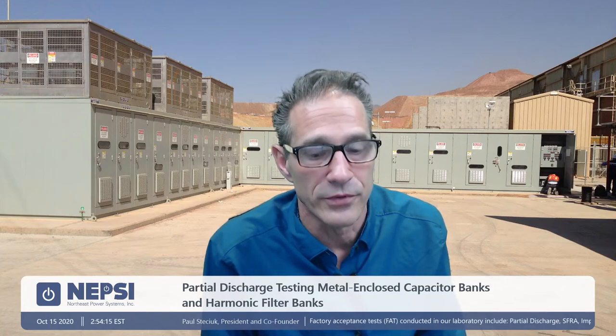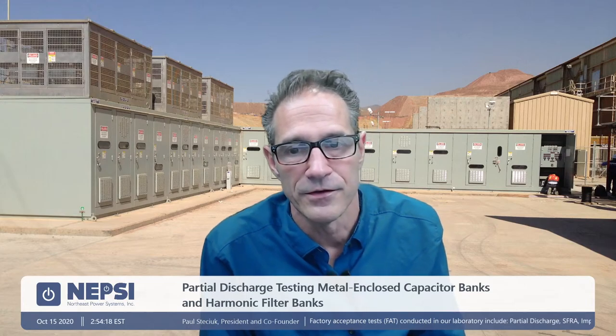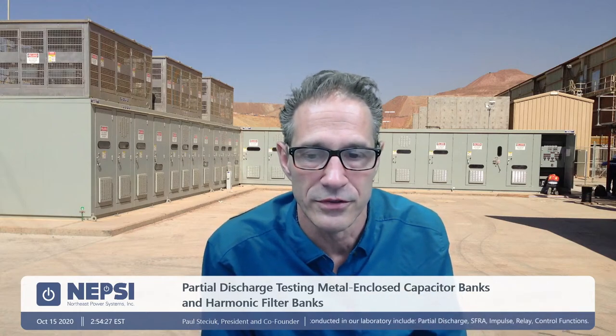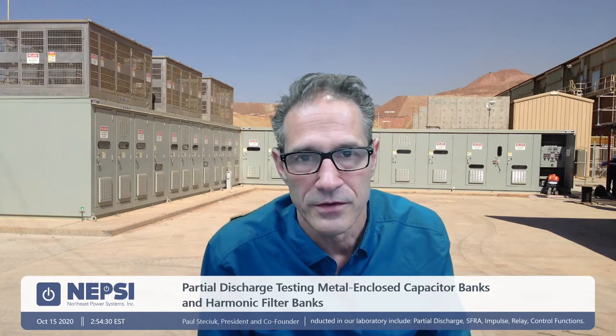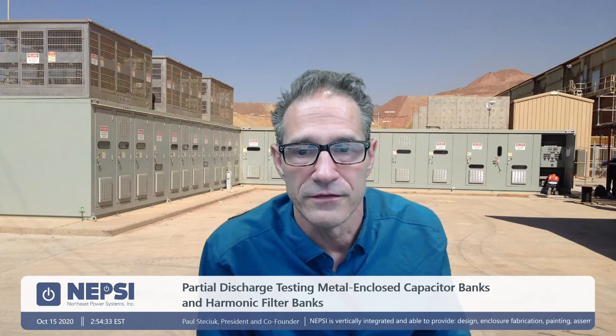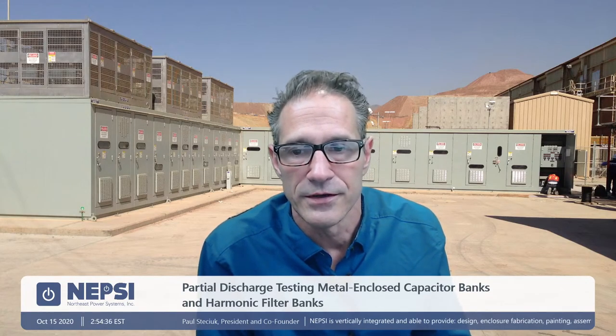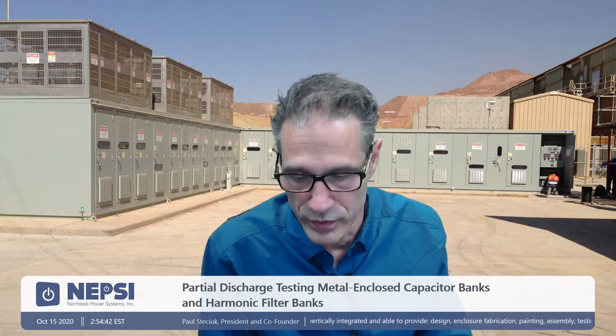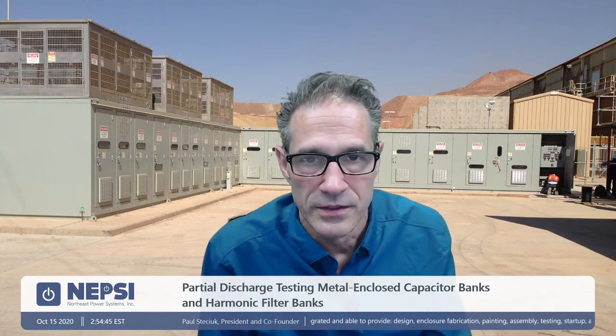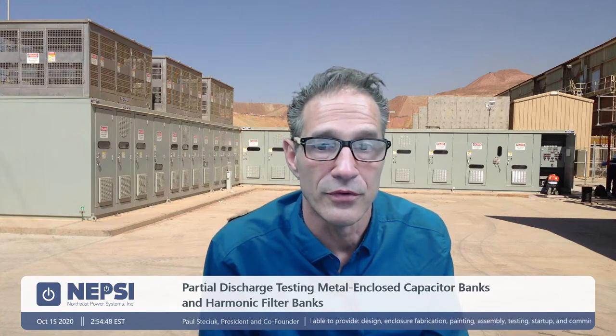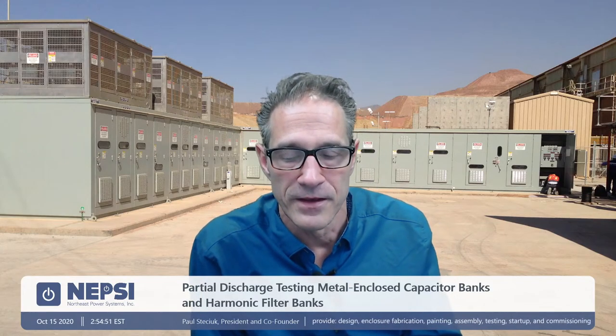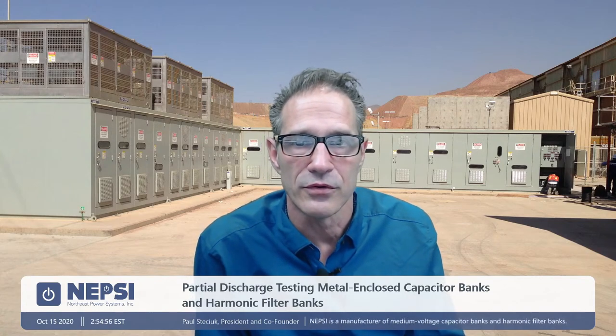So if you take a piece of jumper cable and you lay it at ground potential, you will have partial discharge in that cable or along the edge of that cable, and this device would pick it up. Same with the pass-through. If it's not done correctly, you will detect it, as well as voids within bushings. So we have been able to identify issues with the equipment at this 38 kV voltage level and below on many occasions. We have also witnessed equipment in the field, equipment that might be 10, 15, 20 years old, where there has been partial discharge activity, tracking along insulators and so forth. So there is a lot to be learned from doing this test.